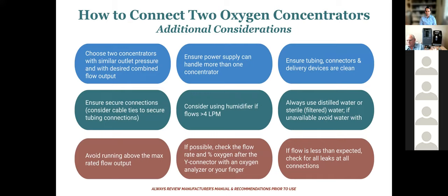Think about securing your connections with cable ties, zip ties, so make sure they don't come off. There's just more potential places for error in this. And then otherwise, similar recommendations as we previously discussed: when to consider humidification, avoid running above the max rated flow, and then check for leaks. If you connect to the patient and this seems less than what you'd be expecting, look for leaks, look for resistance, and troubleshoot those as they come up.